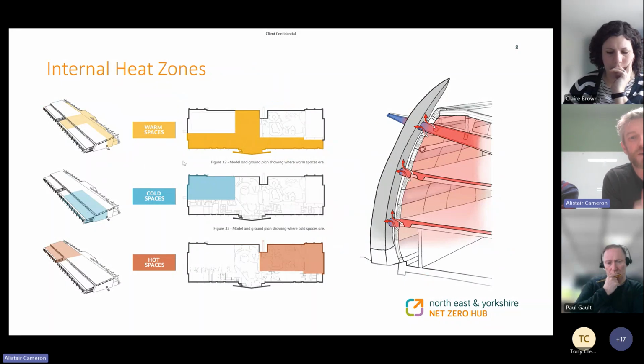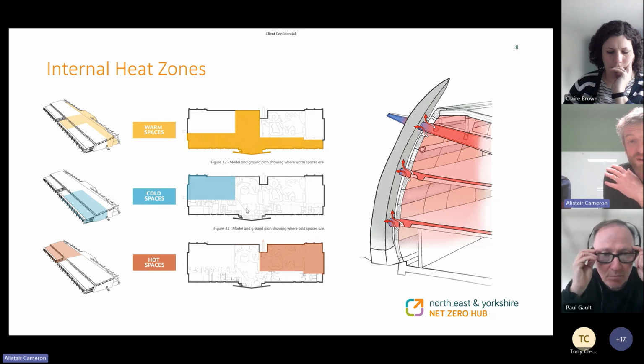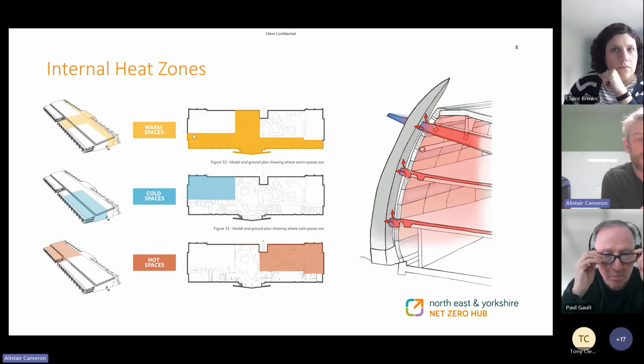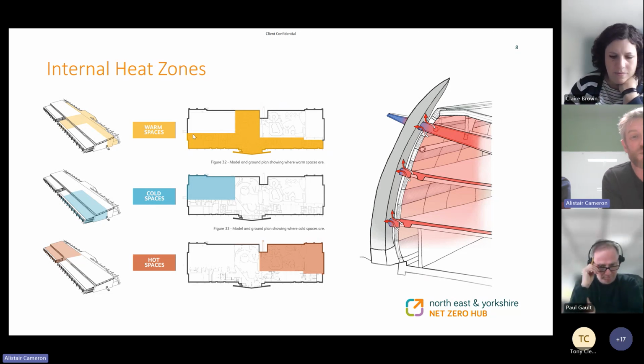We've got this kind of warm space area at the top. These are the kind of offices and, you know, ancillary spaces, but the building also has a number of hot spaces. We've got a swimming pool in the building, which obviously generates a lot of heat, and there's a proper swimming pool with lanes, but there's also a kind of play area too. In the centre there where the warm space is, that's a gymnasium there. And then to the left-hand side, the cold space, they'd actually retrofitted an ice rink into the building as well. So again, in terms of solar gain and heat loss in the facades, we've got issues there, or an imbalance rather. But then when you look at the internal heat zones as well, there's a complete imbalance there where we're generating a lot of heat in one part of the building, we're trying to lose it in another part of the building. So it's really quite a complex scenario that we're looking at in that building.